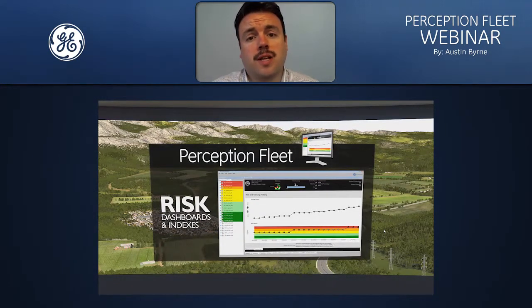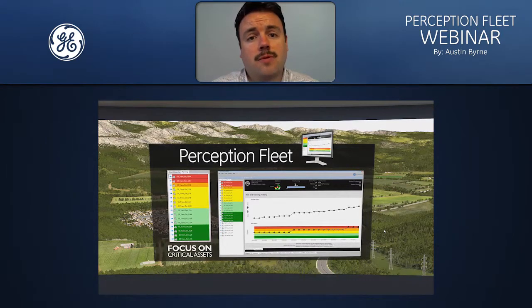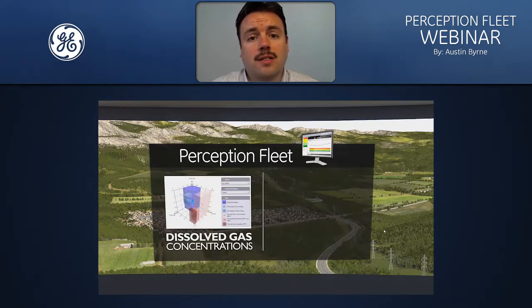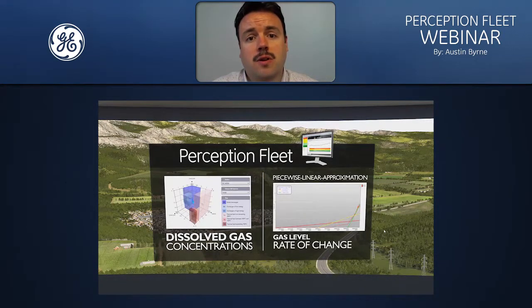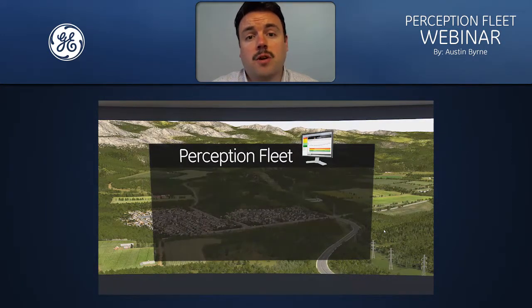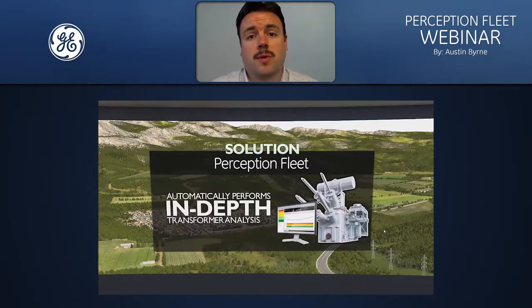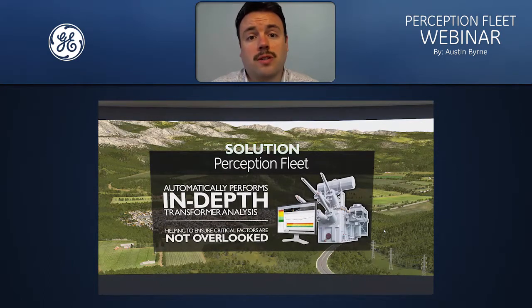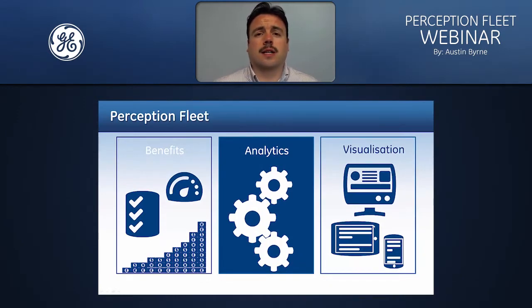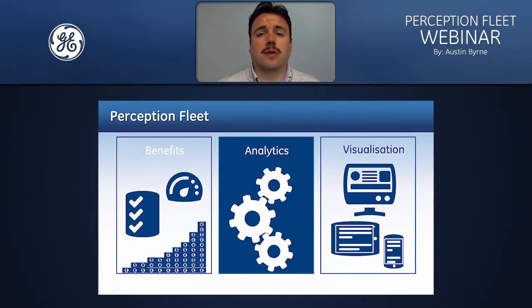Perception Fleet's risk dashboards and risk indexes help focus the utility on the assets that require attention. The algorithms analyze dissolved gas concentrations and utilize techniques such as piecewise linear approximation to determine gas level rate of change. Perception Fleet automatically performs in-depth transformer analysis, helping to ensure critical factors are not overlooked. Next, let's take a look at the analytics performed in Perception and how it evaluates and interprets the data received.